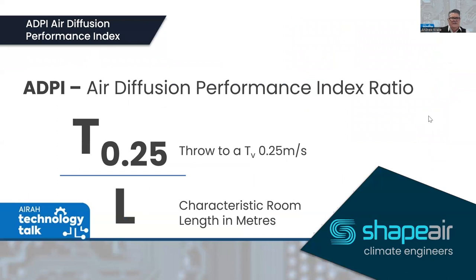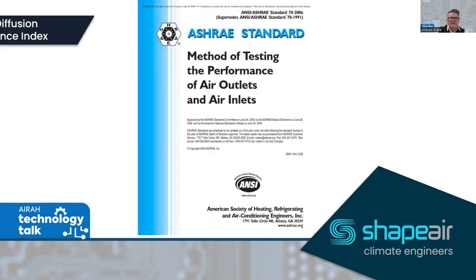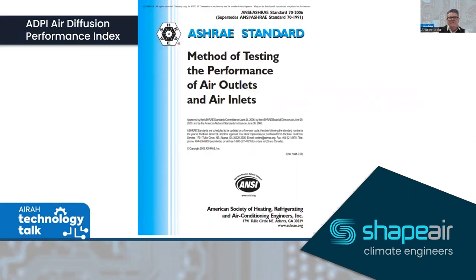The ADPI method uses the formula: throw to 0.25 m/s divided by the characteristic room length (T₀.₂₅ / L). This is used to either design using the ADPI method or to validate a design. To do this, you need air diffusion equipment tested to ASHRAE Standard 70.